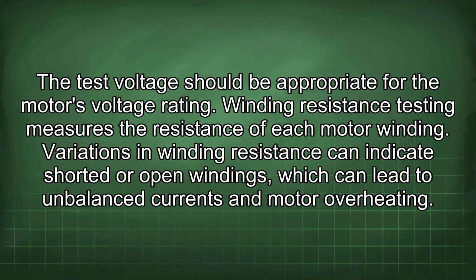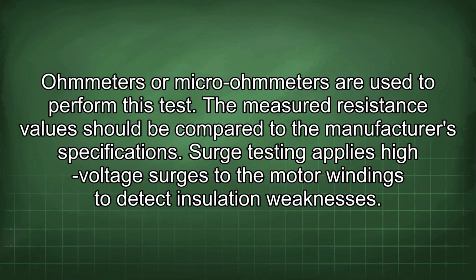Winding resistance testing measures the resistance of each motor winding. Variations in winding resistance can indicate shorted or open windings, which can lead to unbalanced currents and motor overheating. Ohmmeters or micro-ohmmeters are used to perform this test. The measured resistance values should be compared to the manufacturer's specifications.